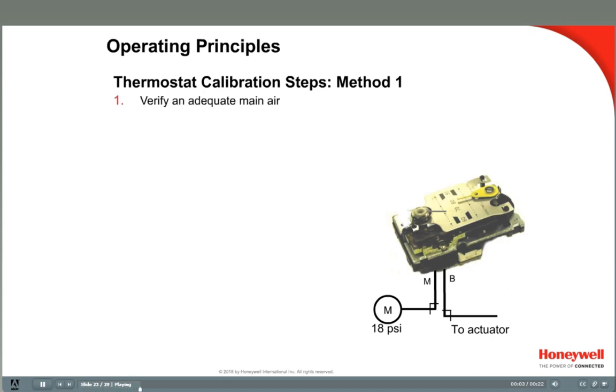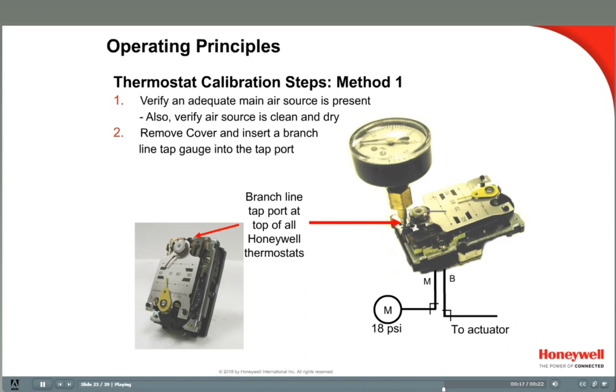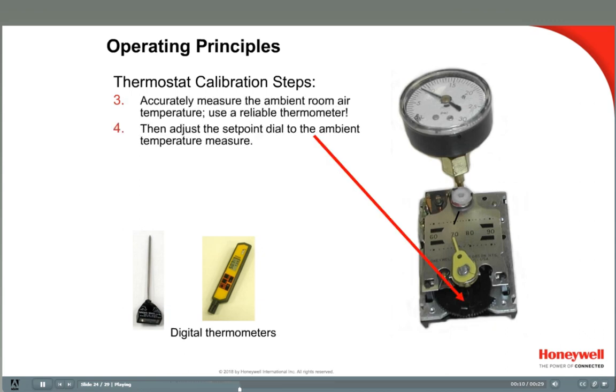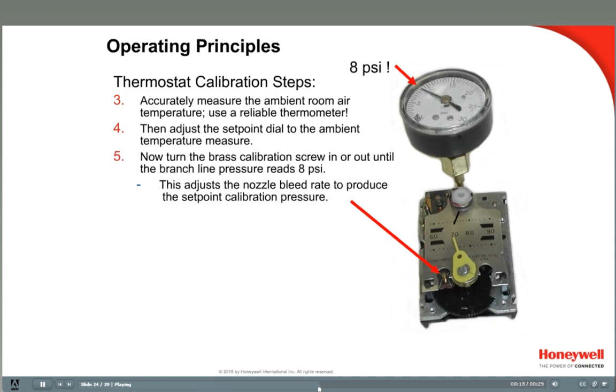Here are the steps to calibrate. Step 1: verify the main air supply at the stat — main air pressure may vary around the building due to pressure drops, but should remain somewhat constant at a given location. Step 2: remove the cover and insert a branch line tap gauge into the tap port at the top of the stat. Step 3: measure the ambient room temperature with a reliable thermometer — do not use the built-in thermometer on the thermostat. In this example, the room temperature is 70 degrees. Step 4: turn the set point dial to the ambient temperature. Step 5: adjust the small brass calibration screw to get a reading of 8 psi on the branch gauge.